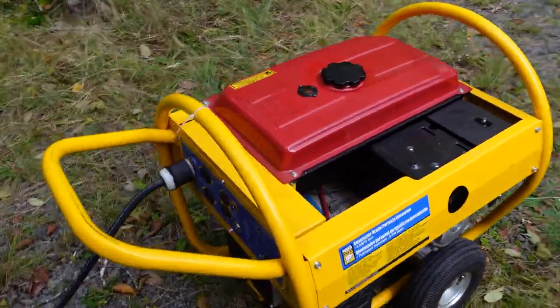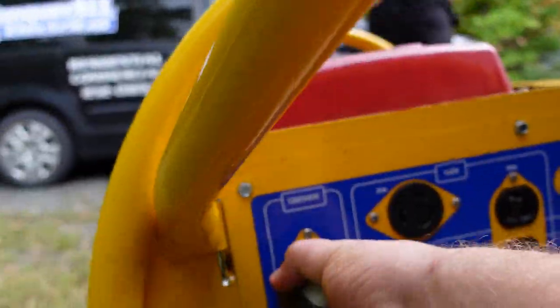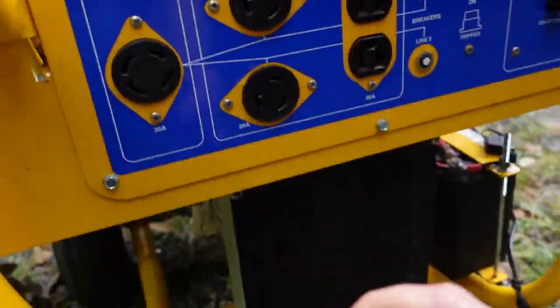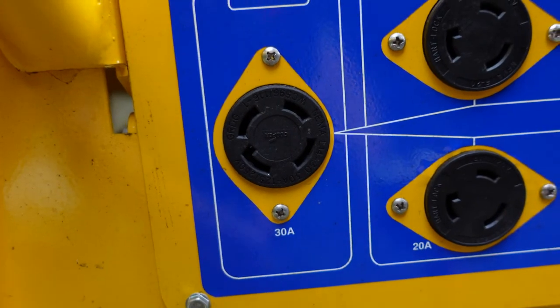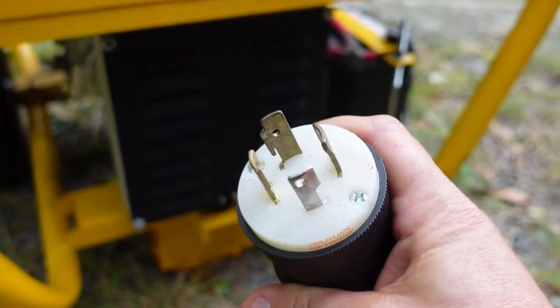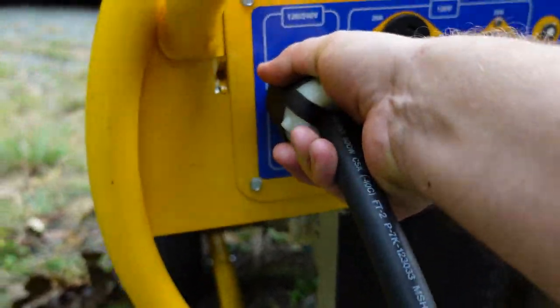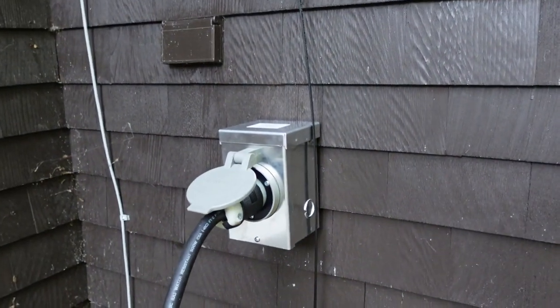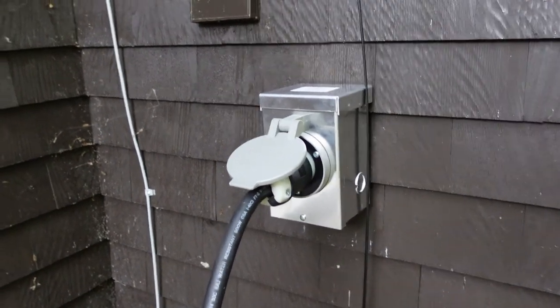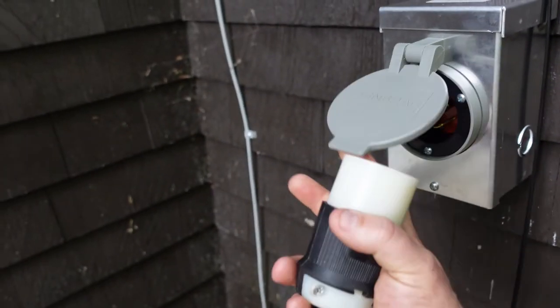Basically, a portable generator that is 5,000 to 15,000 watts with an L14-30R — which is a four-wire twist-lock receptacle that your electrician supplies — plugs in right there. It has a neutral that's keyed so it only plugs in one way: you push it in and twist it, then plug into the outdoor receptacle your electrician has supplied, which connects to the generator side of the manual transfer switch on the generator panel.